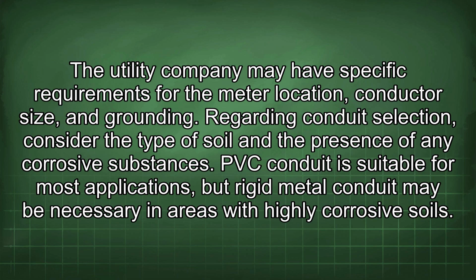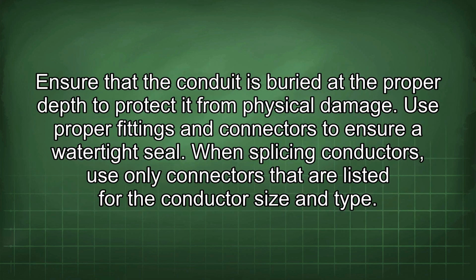Regarding conduit selection, consider the type of soil and the presence of any corrosive substances. PVC conduit is suitable for most applications, but rigid metal conduit may be necessary in areas with highly corrosive soils. Ensure that the conduit is buried at the proper depth to protect it from physical damage. Use proper fittings and connectors to ensure a watertight seal.